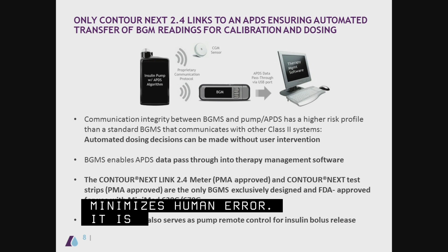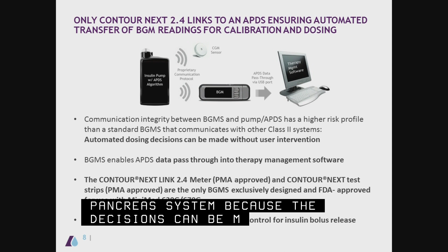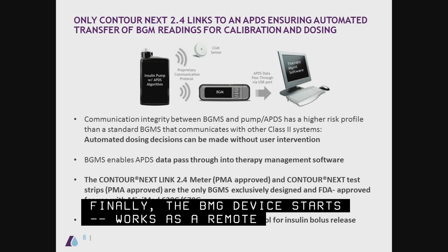Another factor that plays to the importance of using the BGM device intended for use with the artificial pancreas system is the communication link. The BGM measurement is transferred wirelessly to the pump for the purposes of calibration and dosing, and that minimizes the human error associated with manual entry. The integrity of this data transfer is particularly important in an automated artificial pancreas system, because decisions can be made without user intervention. Finally, the BGM device also serves as a remote to control insulin bolus release. About 20% of type 1 patients forget at least once a day to give a bolus, so this helps to facilitate that as well.